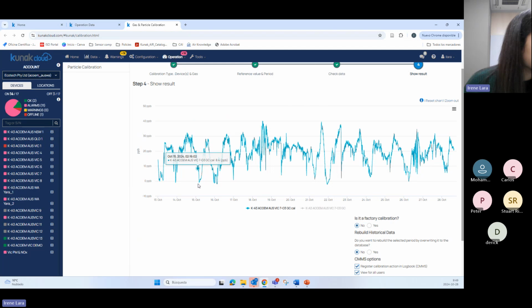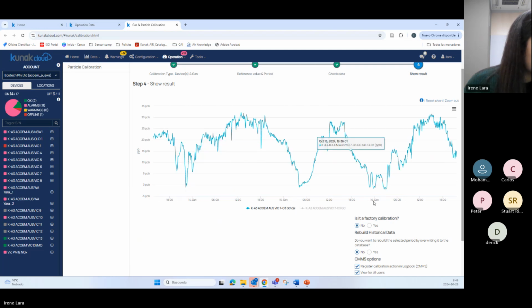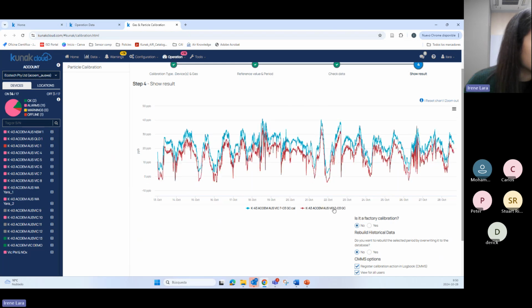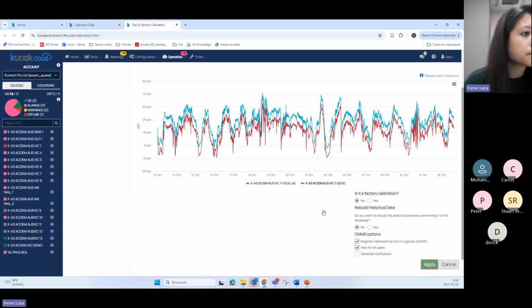And then we can check here this value. These are during night. This, 5 in the morning could be a minimum, and you see it's almost 0 ppb. So it can confirm that the point that we selected was the correct one. Okay, and now you can see the difference between the raw data and the calibrated data.